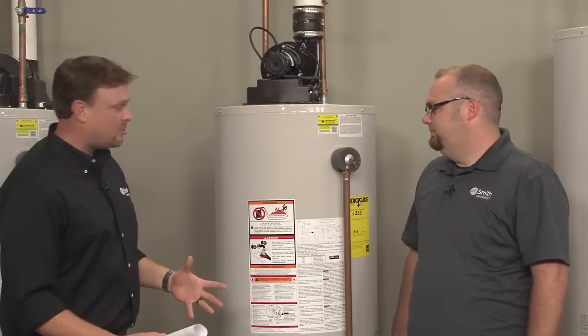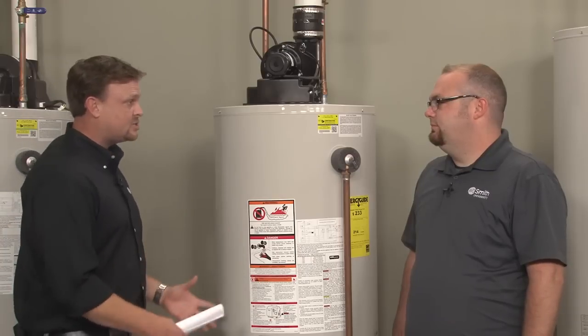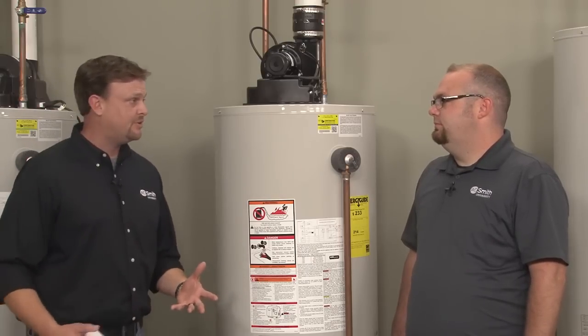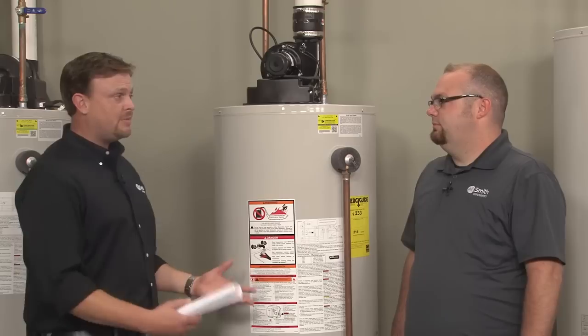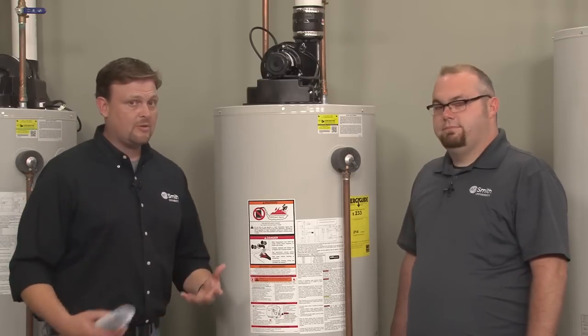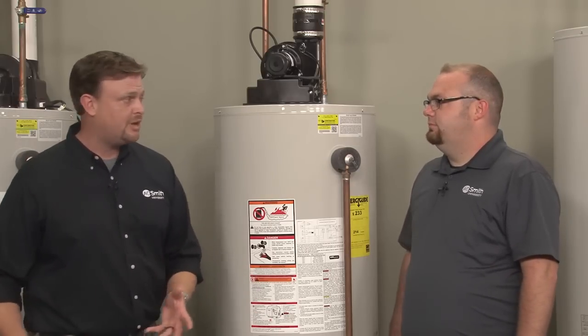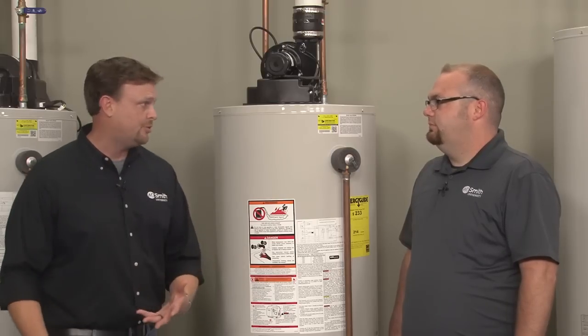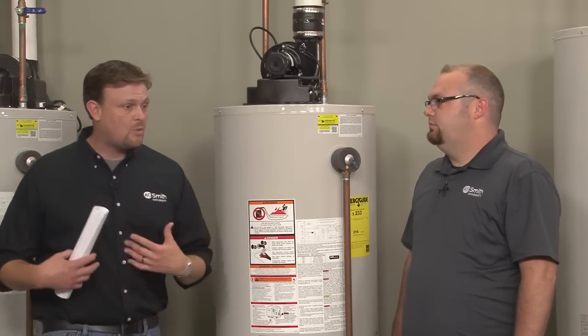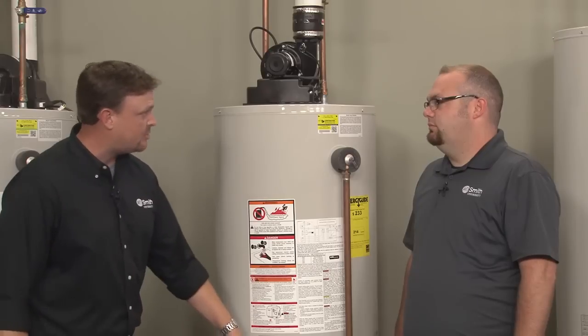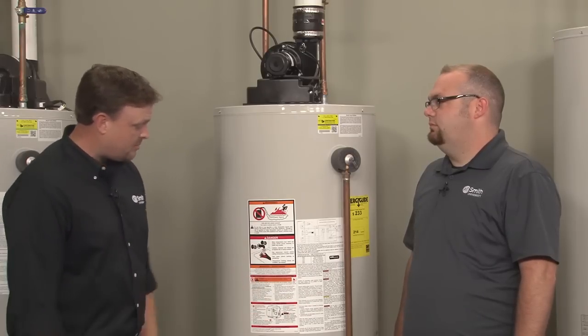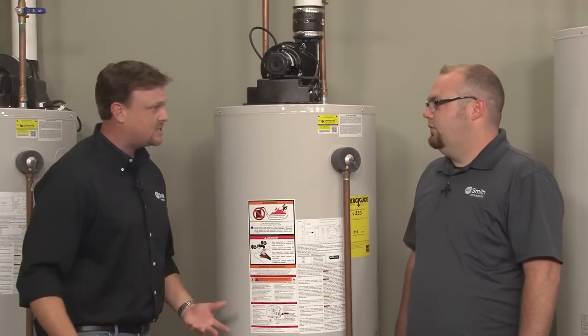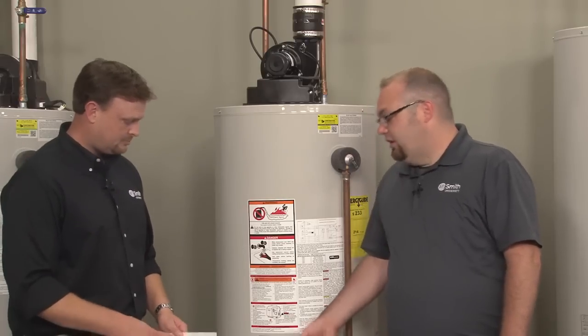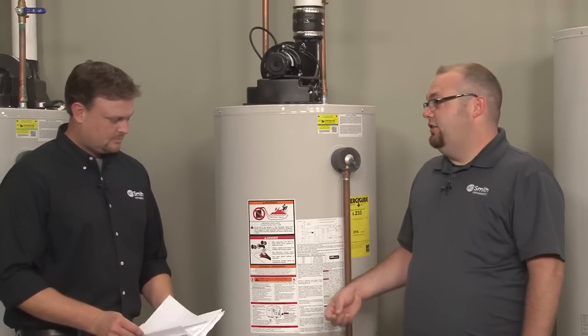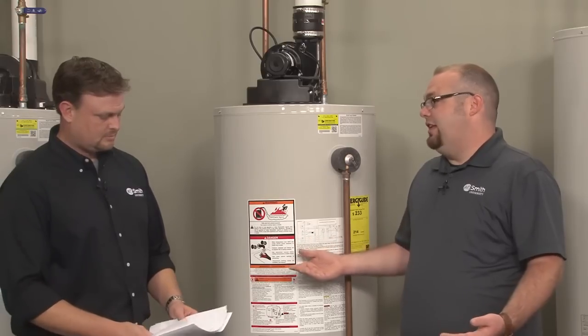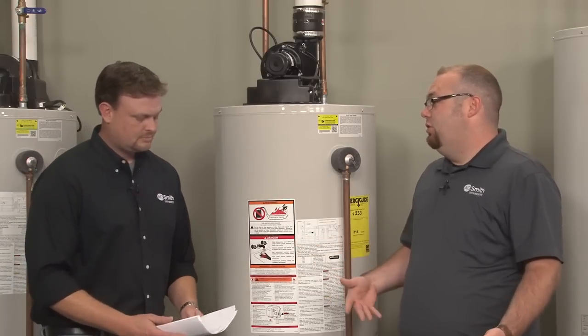Okay, the next thing I want to talk about is a 6.1 error code, or an ignition failure. Now this is typical on maybe a new install that you might run into something like this. That means the water heater tried to fire but never could. Correct. So if I walk up to a unit and I see a 6.1 flash on my Honeywell gas valve, what am I supposed to do first? All right, 6.1 flash, like you said, it's telling you the heater tried to light and either lit or it didn't, or it may have lit but didn't prove that it lit.